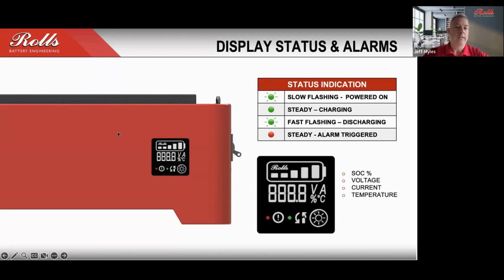In the case of an alarm, as an example, if it's an overvoltage or overcurrent situation that's triggered, chances are the alarm is going to be shown on all of those units in the stack. However, if the alarm goes off on an independent one, then that's possibly due to an issue specific to that unit. Typically, if you're seeing a condition that's outside of the constraints that have been set by the BMS, then you would see all of the units showing that alarm. When you do see an alarm, you have a couple of ways to retrieve the information to determine what that specific alarm condition is.